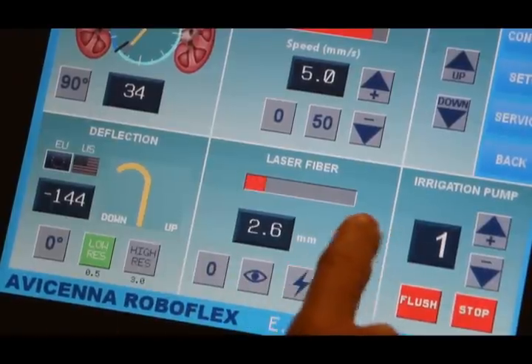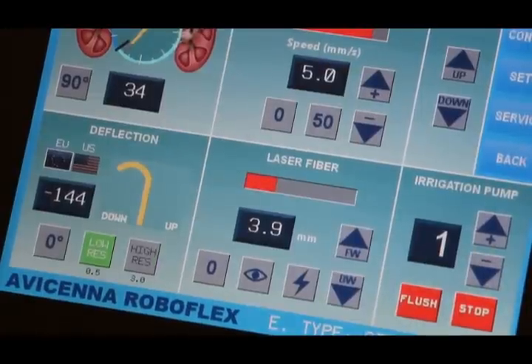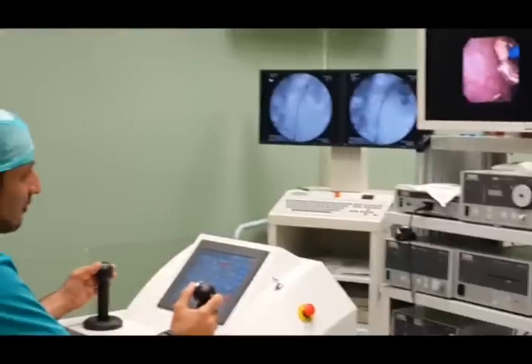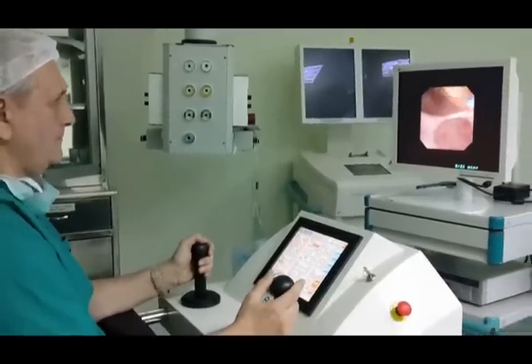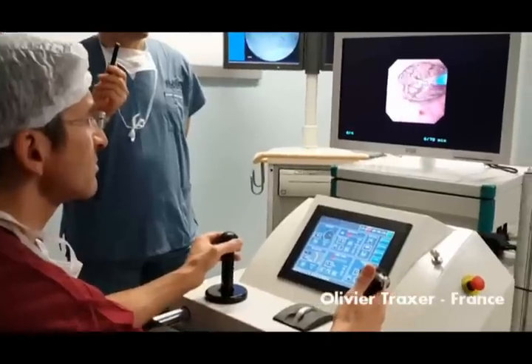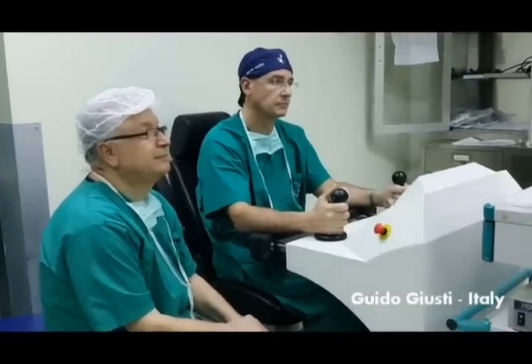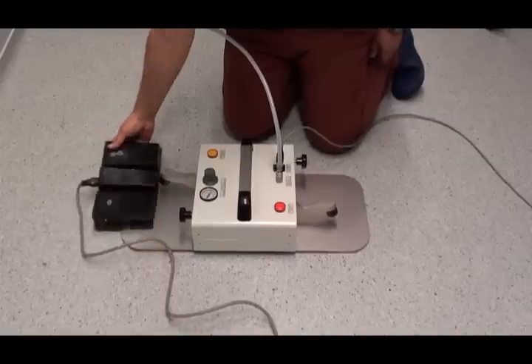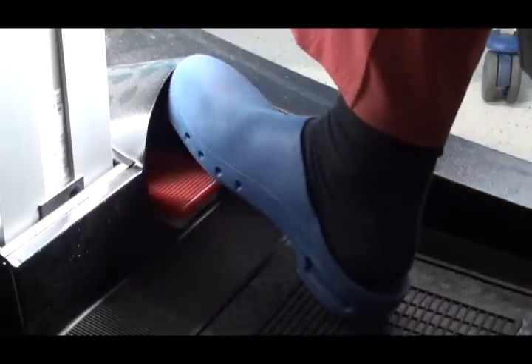When the progress bar colour changes from blue to red, it is safe to activate the laser. The fibre can be advanced via the console touch screen to the precise distance required from the stone surface, a feature that gains importance when treating soft tissue lesions such as urothelial cancer of the upper urinary tract. When the tip of the flexible ureterorenoscope is near the stone and the power button is pressed, the tip of the laser fibre is automatically advanced to the nearest firing position. Further advancement can be performed using the in-out controls, and foot pedals for laser and fluoroscopy are remotely controlled with the new universal remote console pedal control unit.